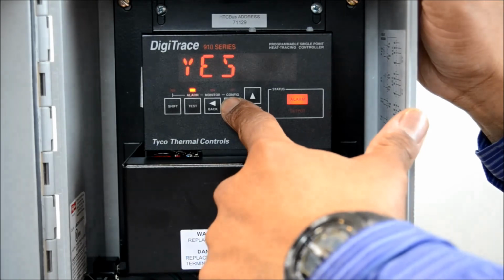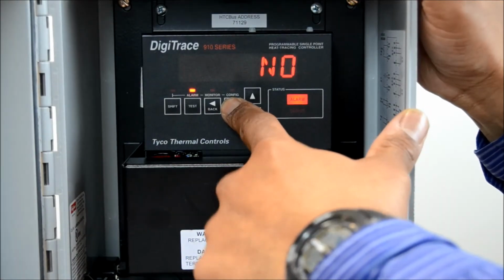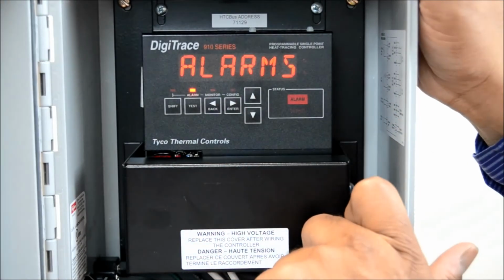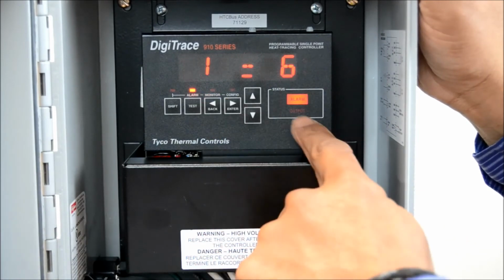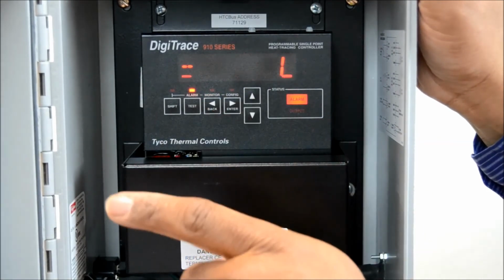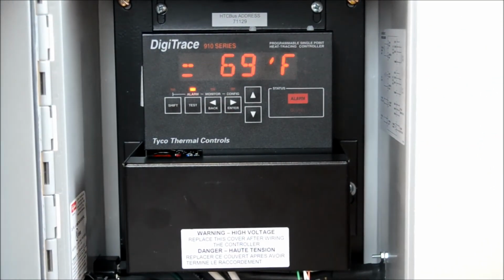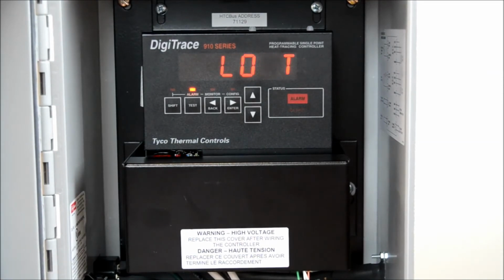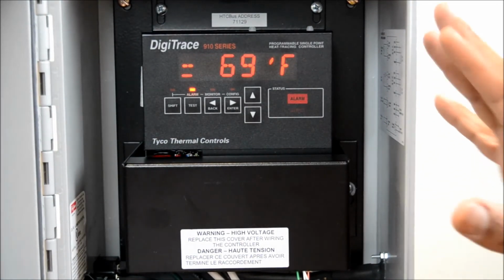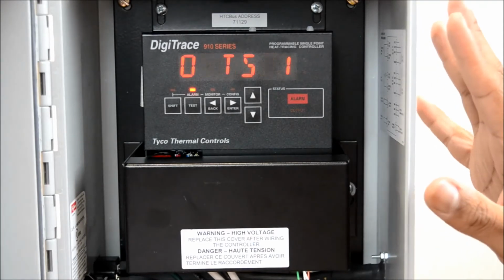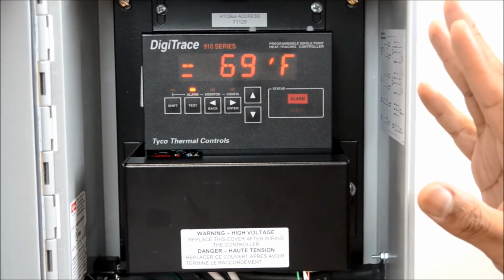So yes, I want to reset it, so I'm going to hit enter again. It says no alarms, right? But it popped back on again. The reason for this is because I did not clear the alarm first. So a lot of these alarms that you get on the controller, you're going to have to clear first.